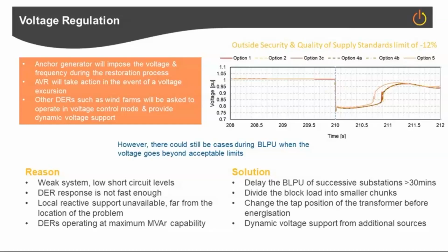So that reactive response, that voltage response that you need to capture the drop in volts and restore it back to nominal, potentially you need additional assistance from other sources of DER within that group to provide you a stronger system. We've done some other work on energization of transformers. What we found is energizing up from 33 kV networks, which is the typical distribution network voltage level that we're looking at here, up to the grid voltage of 132, and then up again to transmission level, which in GB is 275 and 400 kV. So we've done a bit of analysis around that.